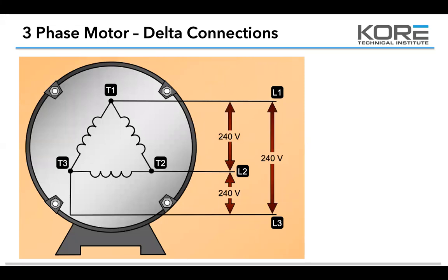If you test these and you have good voltage sending from your contactor, but the motor's still not running, you're going to want to disconnect those leads from the motor, and you're going to want to ohm out the motor. So has anybody used a mega ohm meter?